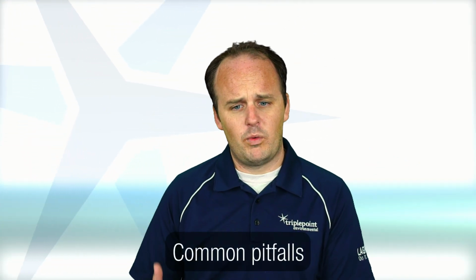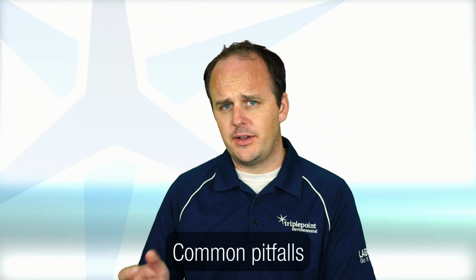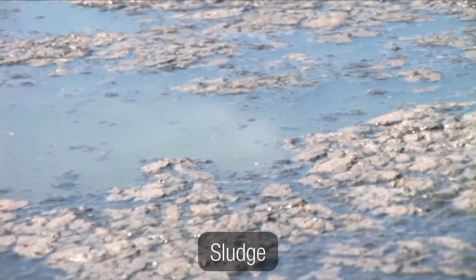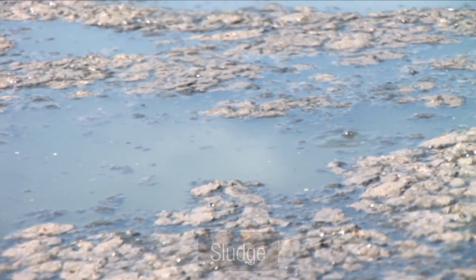So finally, the common pitfalls that we see. Well, one thing we see a lot of is that people fail to account for sludge. And sludge throws two curveballs at you. Number one is sludge is, in some cases, undigested BOD. So you could have aeration out there pounding away at the water, and it could still see a DO of 0. And you scratch your head and you're like, why is there a DO of 0 out here if we're pounding away with our aeration?